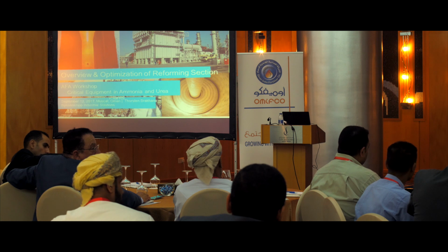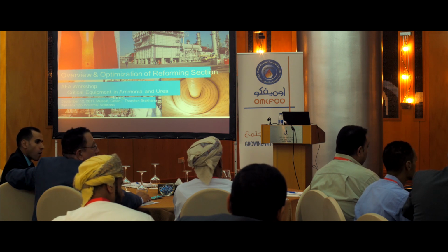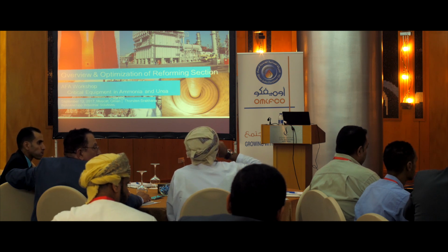In the last slide, you showed the options for vaporization, right? Yes. You used electric heaters and fans, and another way of heating as well. Yes. The last one was the low pressure steam. If you use heaters and fans, you will consume a lot of energy, right? Yes, that's the reason I don't like to use electric heaters, because you need a lot of electrical energy. That's why we use it only for a very small unit, which is hardly running. But the advantage is you have fans which are running cold. The second option is using flue gas from the convection bank, where you have hot running fans. That can cause some problems with the fans, because they're running at maybe 400 degrees C. And if you have steam available, it's the simplest option. Yes, if you have steam available. Thank you. You're welcome.